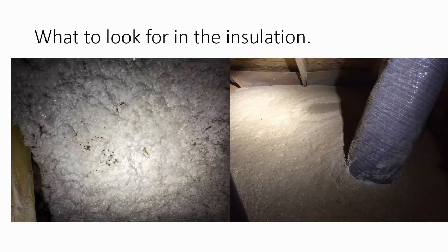And in both those situations, what's happening is the air is rising out of the house, hits that top layer of the insulation where it freezes, gets cold. If it's cold enough, that gray spot will actually be frost. If it's in a warmer temperature, then we'll see that dark wet spot. And it's so pronounced that I'll be in attics sometimes and I can actually count the person's pot lights in their kitchen because it'll be a round circle over top of every single one. You'll go to another darker wet spot in the insulation, put your hand down and you'll see a wire penetration. It's black and white. It's air leaking out those holes.